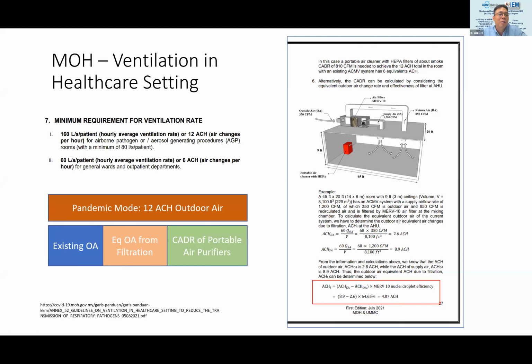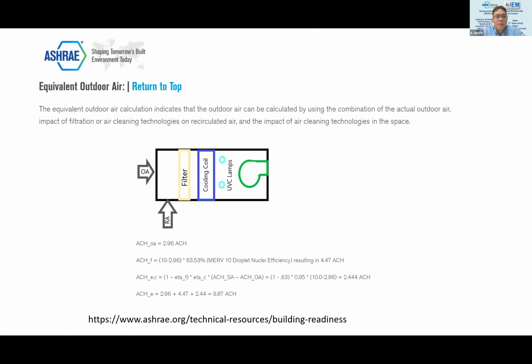That's why we see some COVID wards have portable air purifiers inside, because they use this formula to compute the actual 12 air changes that are required. Okay, and then there's this building readiness recommendation from ASHRAE at the peak of the pandemic, which actually uses a concept of flushing. The equivalent outdoor air is used for flushing.